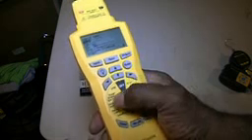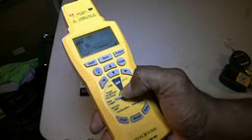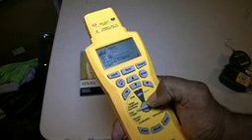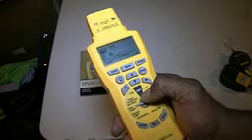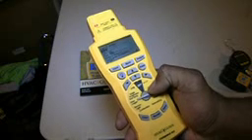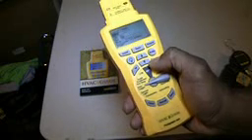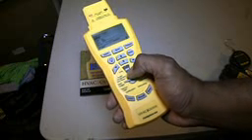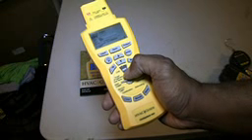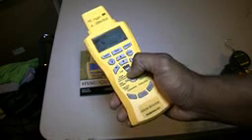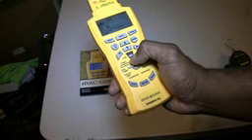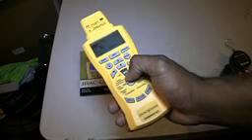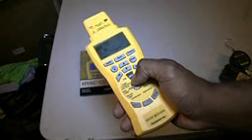Now, one cool feature that I do like about this HVAC guide is the data logger. For the most part, with the data logger, I can sync up to 13 wireless devices with this thing. Okay, I'm sorry, 12, and then this device here will be the 13th. Let's say, for example, I wanted to do an overall check of the AC unit. I can check supply dry bulb, supply wet bulb, return dry bulb, return wet bulb, humidity, delta T.